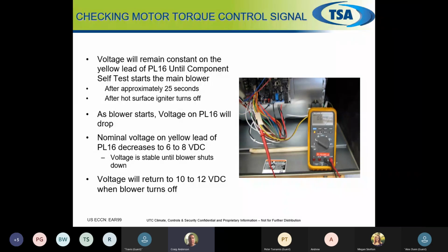coming from that motor. If we're getting significantly lower, then we know this is the feed from the motor. If our power on our yellow is wrong, then we know something is going on with our motor, not our board, because our motor is talking to our board at this point. If we're on the brown and our powers are funky, then we know we're dealing with a board issue, because our board is talking to our motor. So once you get that set up, brown's talking, yellow is coming back, that gives you an idea of what you should be looking at and how to test.